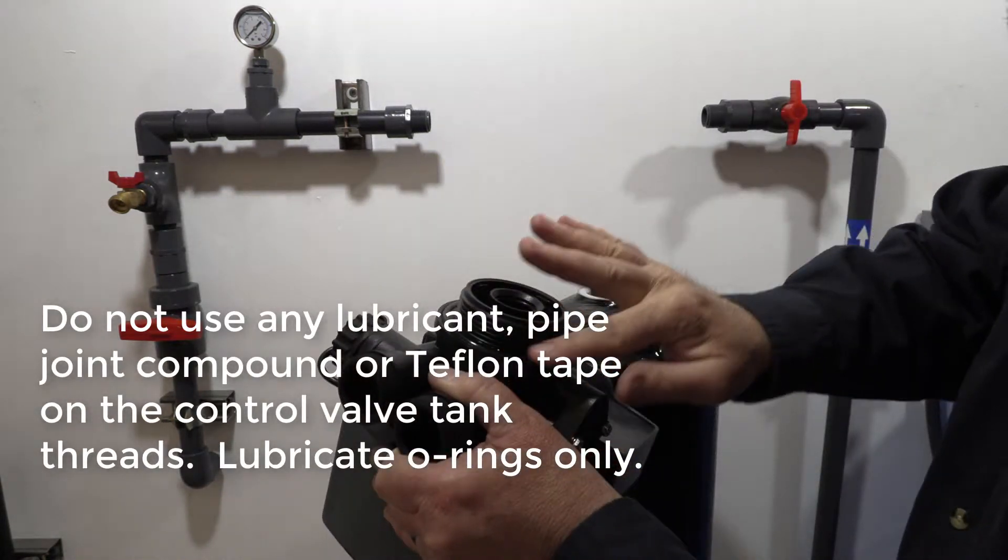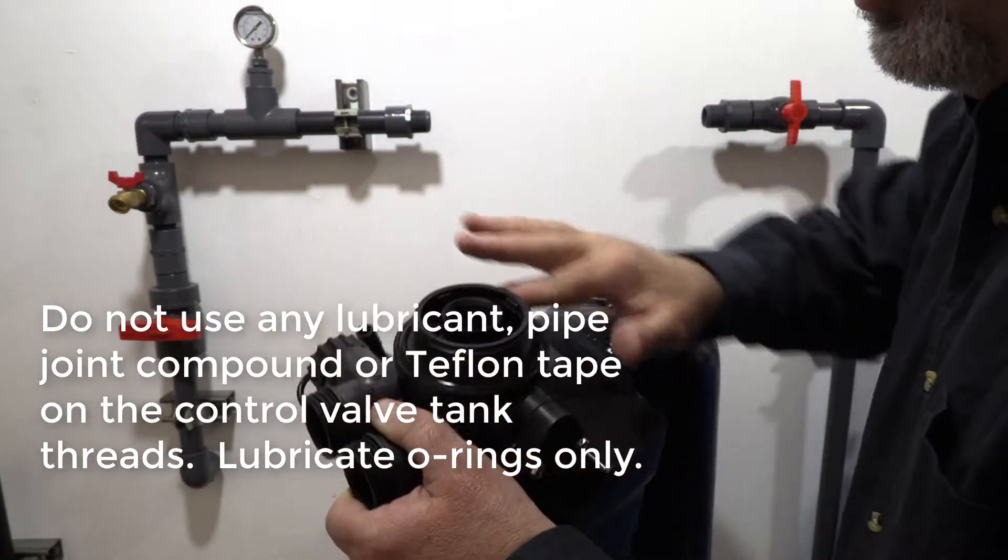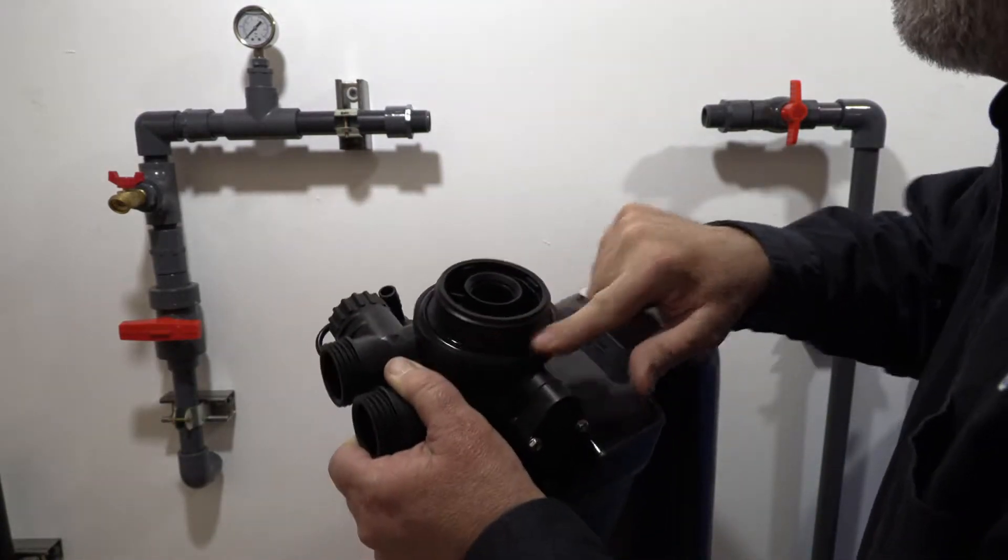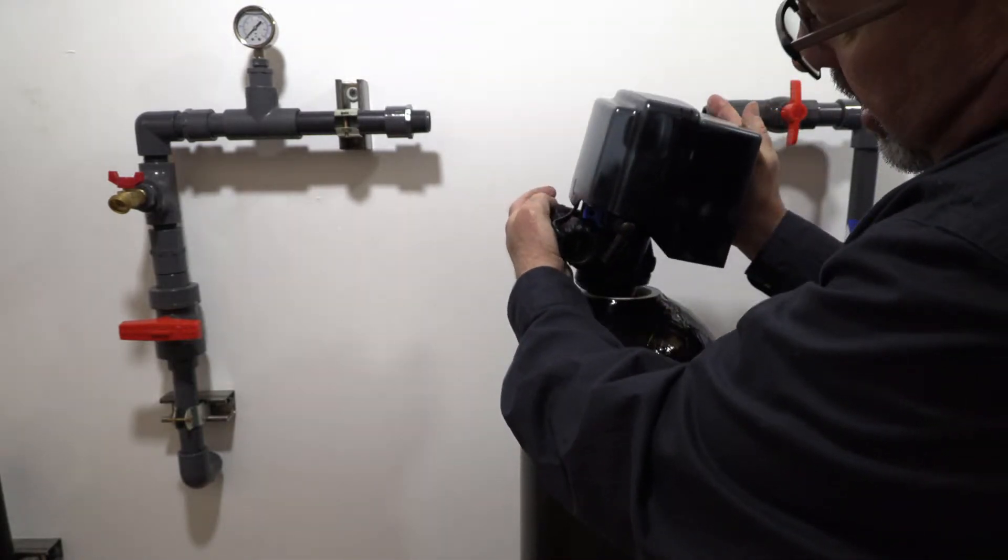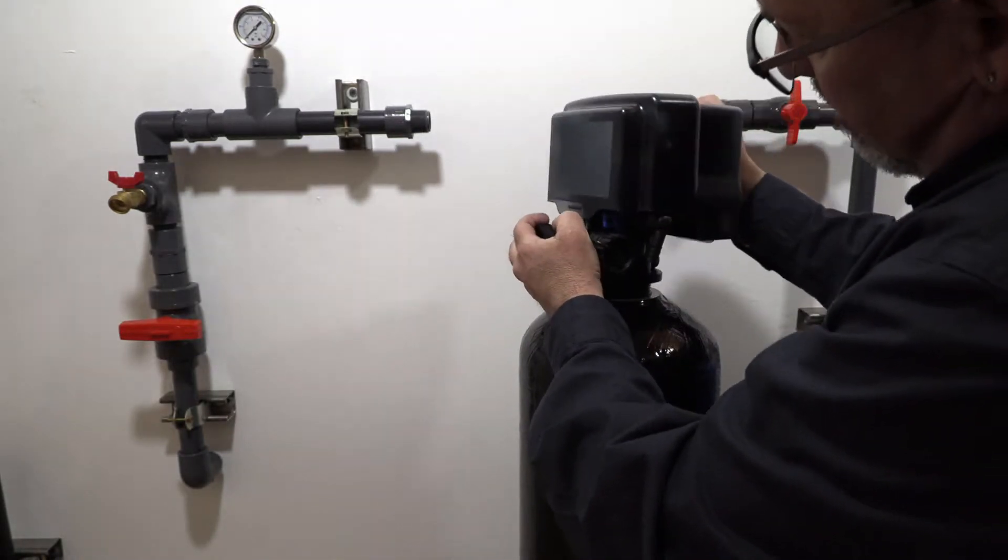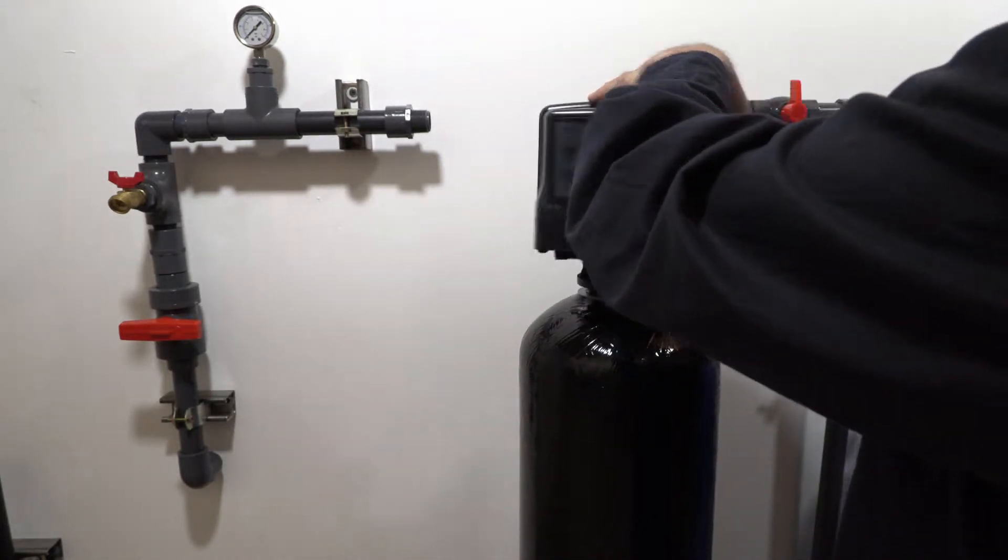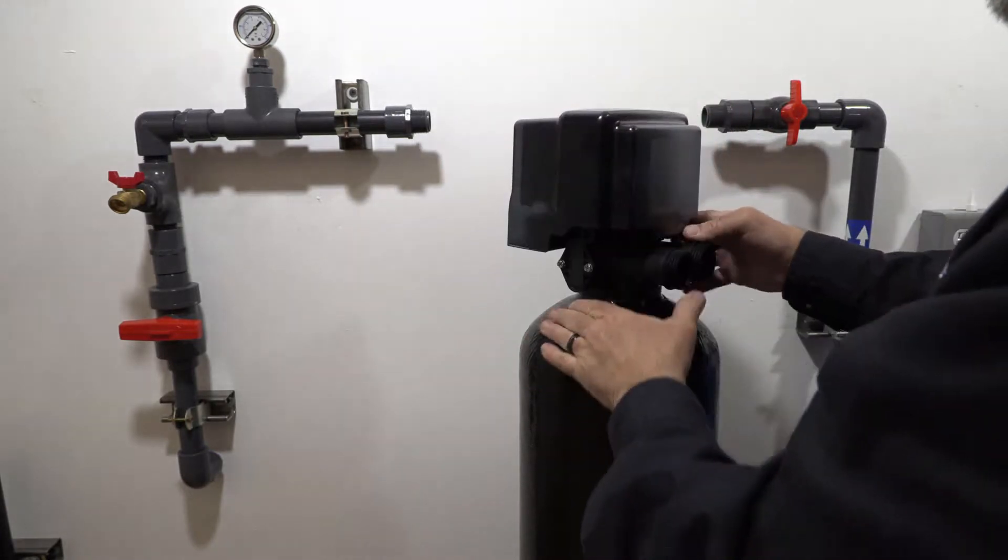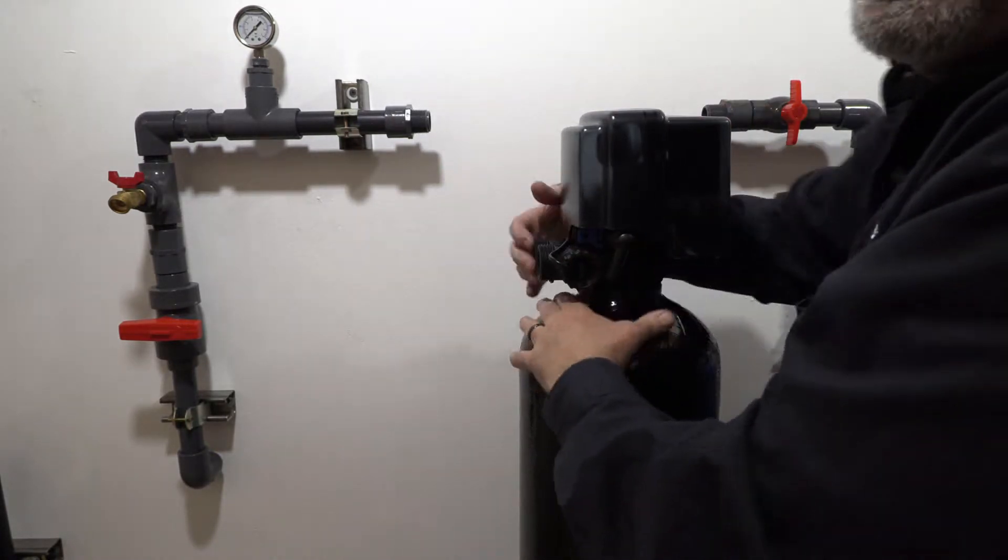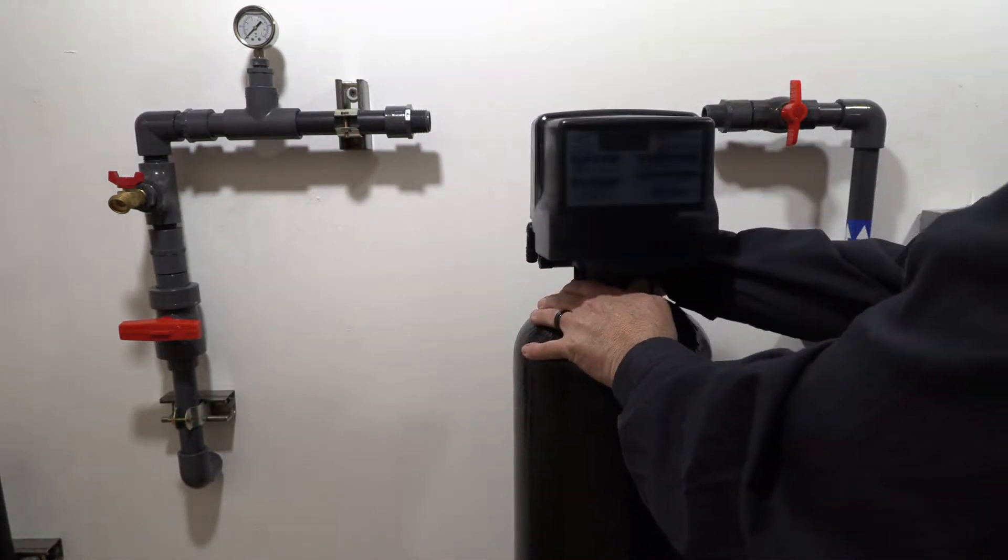You want just a nice little film of this lube all around on the o-ring. Then carefully install this, feed the D-tube up in there, and thread your valve on. It's important: don't use a strap or any kind of wrench on this. Hand-tight is all you need to seal that o-ring.